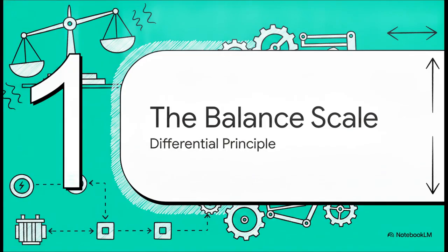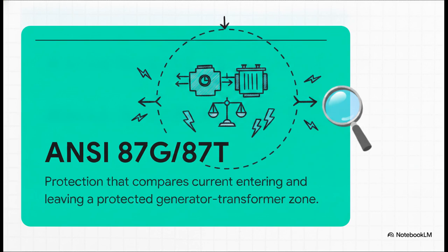Section 1, the balance scale principle. To get just a little technical for a second, we're looking at the ANSI 87G and 87T standard. This is a highly specific protection mechanism. Its entire purpose in life is to establish a strictly protected zone, typically wrapped right around a generator and a transformer, and meticulously compare the current entering that zone with the current leaving it. It acts as this absolute unblinking boundary monitor.